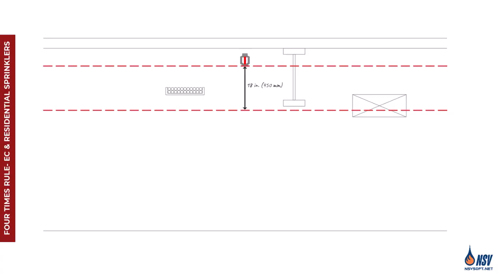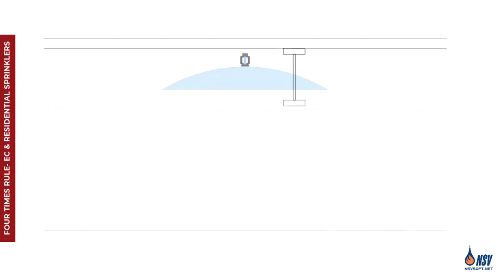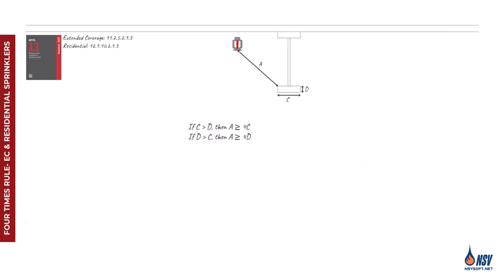For extended coverage and residential sprinklers, when obstructions are located within 18 inches vertically from the sprinkler deflector and water can pass on both sides, the four times rule shall be applied. In this case, the greater dimension of the obstruction is used to calculate the required clearance.